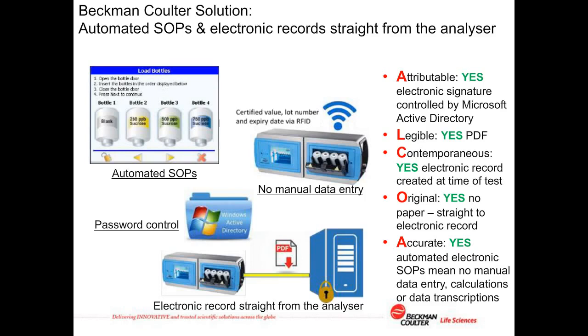We have one more question. Can you download a record in PDF directly from the instrument at the point of use? Yes, indeed. The analyzer does have a USB port on it. So if you were to do manual grab sample analysis or even a calibration, the PDF files can be created instantly and exported via USB. So you can collect it from the analyzer if you choose to do so.